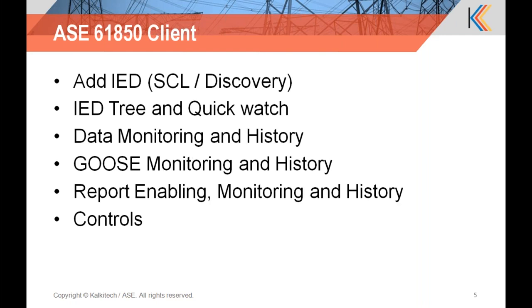On the client side, we will have the add IED feature. IEDs will be loaded into the client system through an SCL file. We will browse the IED tree and see the quick watch feature so that you can view the data points very easily. Further, we will see the data monitoring functionality and history of those data points. We will also extend our demo to GOOSE monitoring, history, report enabling, monitoring and history, and finally the controls.